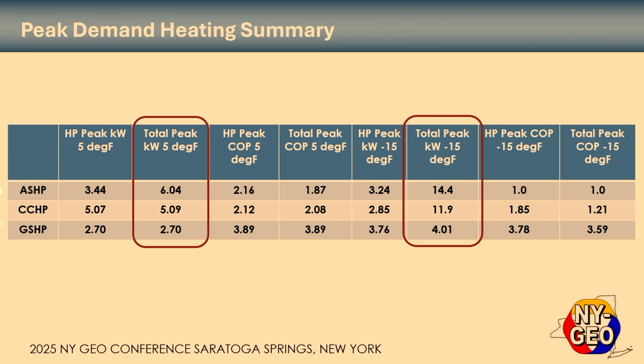The air source heat pump, on the other hand, went up because it has some auxiliary electric heat coming in, and so it's gone from 3.5 to 6. But 5 degrees really isn't the story because from a utility perspective, you really want to look at minus 15 because that's what they've got to supply, or the customer is going to be uncomfortable, one or the other. And so when you start looking at these numbers out here at minus 15, you start seeing the numbers expanding, where now I've got electric heat in both the air source and the cold climate, and the ground source has got a little bit of electric, but not a lot, right? So you can see the separation of the product there.